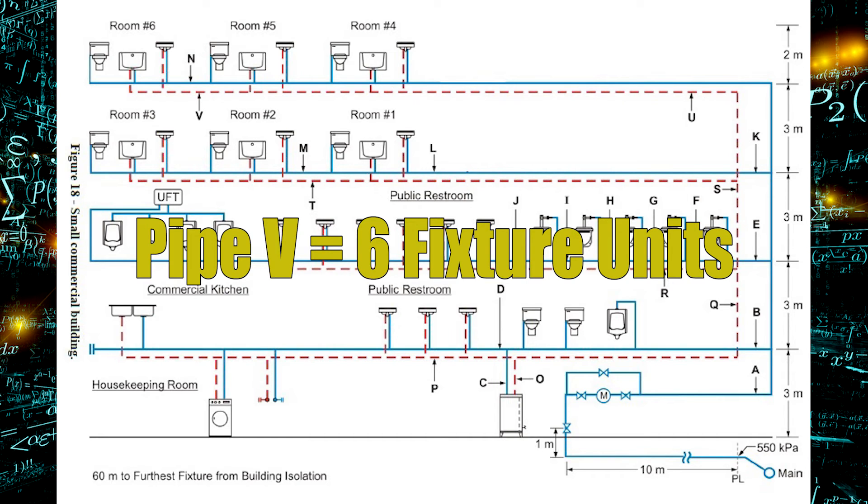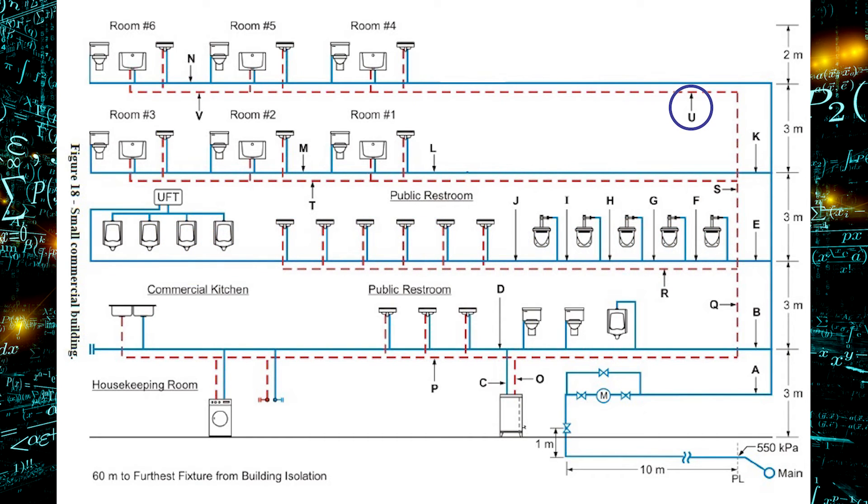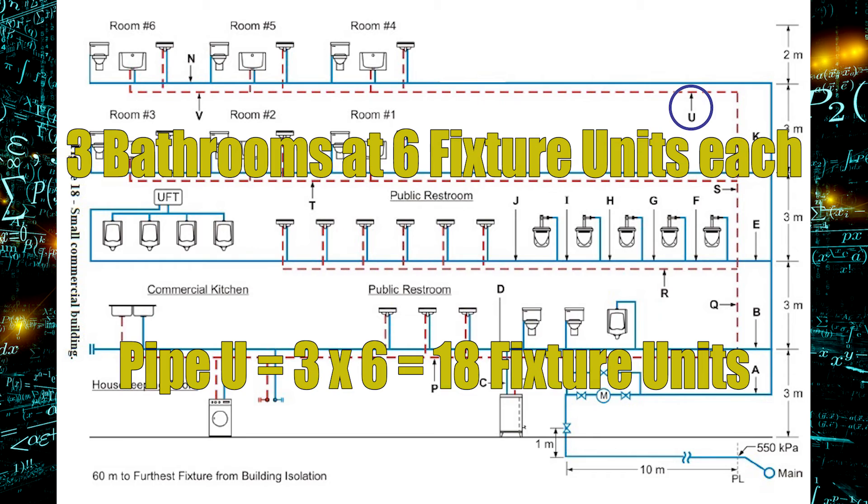If I move over to pipe U, I have three bathrooms now being supplied, and each bathroom was six fixture units each. So that would be 18 fixture units traveling through pipe U, and that will supply the hot water to those three bathrooms upstairs.